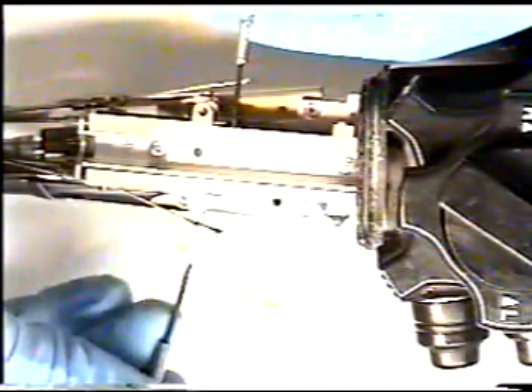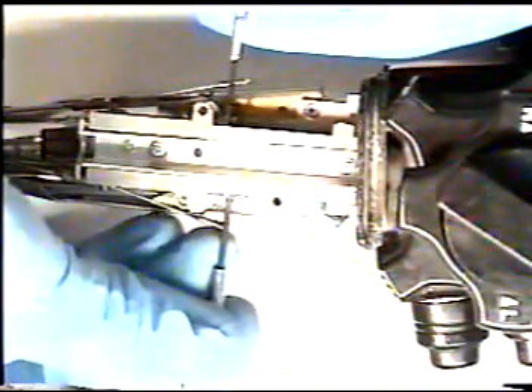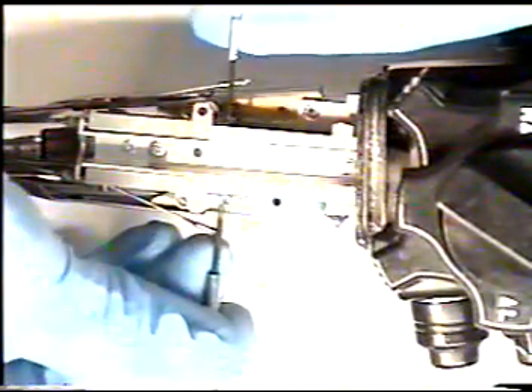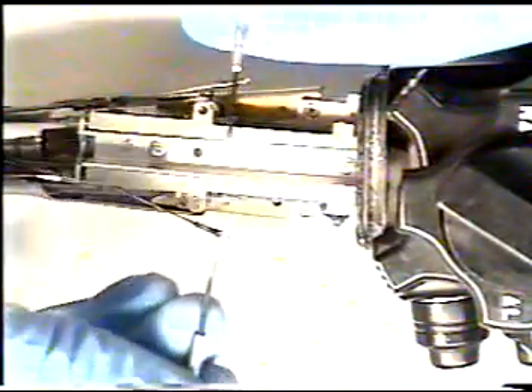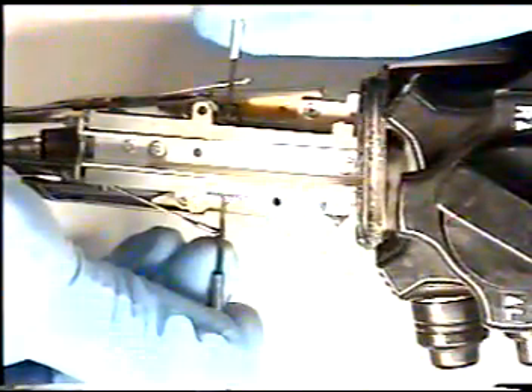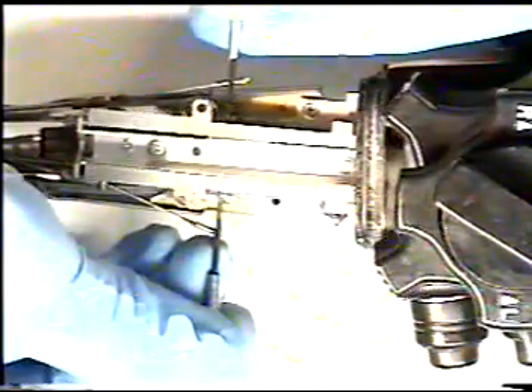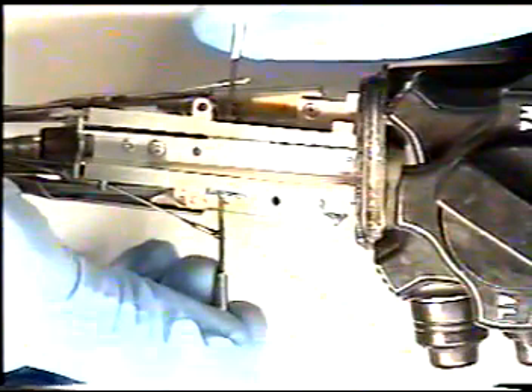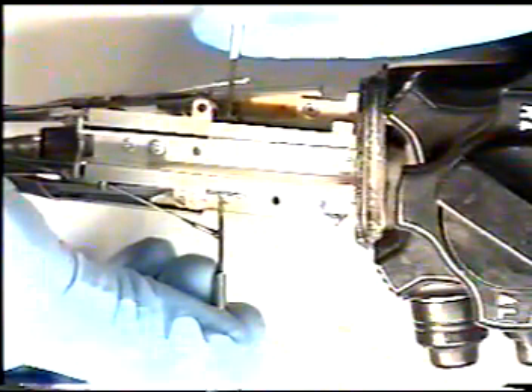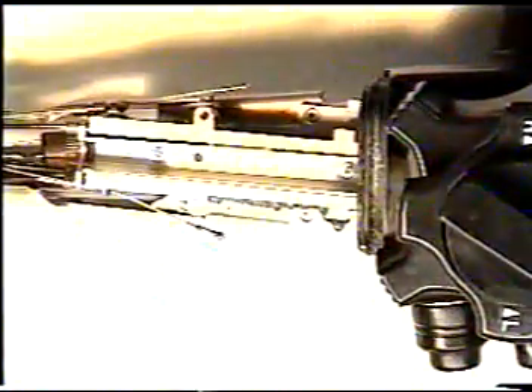Before we actually cut the cable, we must be sure that the angulation chain guide blocks are directly across from each other. Using two number 2 screwdrivers, grasp the back of the angulation chain guide blocks and be sure that both screwdrivers are directly across from each other. As long as the end of the control stopper is now matching the notch in the control block chain guide, we can proceed to cut the play in the cable, which was in this case 2 millimeters.